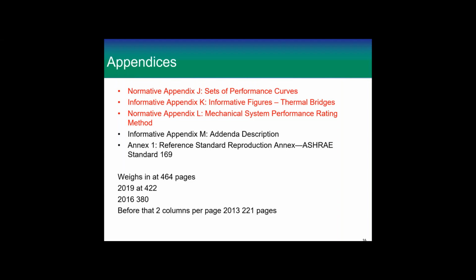Informative Appendix J is a set of performance curves for chillers. If we're going to run models to prove everything more and more, and you can't get a performance curve from the manufacturer because those are secret, they say, if we showed you the curve, our competitors could figure out what we're doing differently than them, and it's just not something we can do. So we made up a set of performance curves with a lot of guidance from manufacturers, and we want you to use those for your baseline buildings.